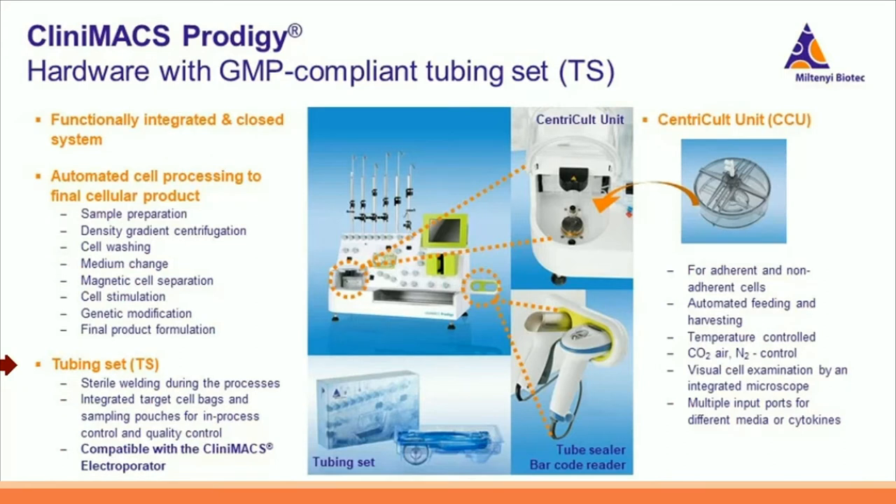The tubing sets are for single use only and completely closed. By sterile welding, users can apply media, buffers, and reagents as needed during the manufacturing process. Furthermore, sampling pouches are integrated in the tubing set so that the user can do in-process controls. The final cell product is harvested in the integrated target cell bags. During the process, cell cultivation is performed in the CentriCult Unit, the heart for cell manufacturing. It supports automated adherent and non-adherent cell culture. In this chamber, the temperature and the levels of carbon dioxide and nitrogen are controlled. Visual cell examination by the integrated microscope is also possible.